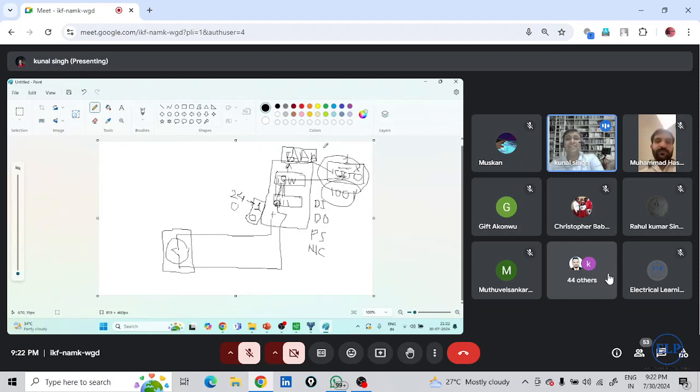And for another protocol, which may be in any other device, like suppose there is a big HMI screen, maybe this HMI supports some software protocol, XY protocol suppose. So it will support the addressing system AAA, and this RTU was supporting addressing system 1000.